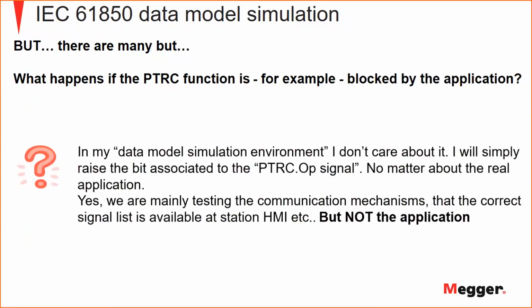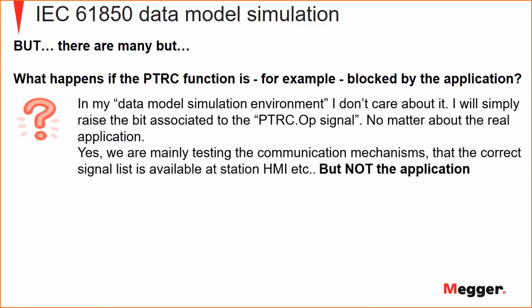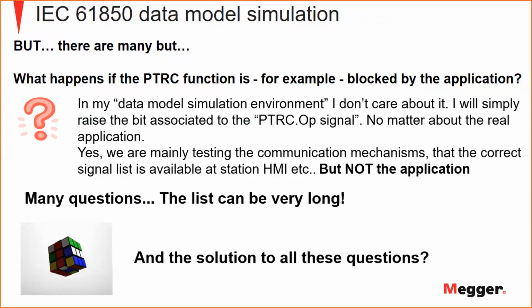And what happens if the protection function is blocked? I go in the data model and I raise a trip signal and I send a GOOSE message on the trip signal. Perfect. Unfortunately, the trip function was blocked. The data model doesn't care. So I hope I'll give you some examples, for more expert and less expert, to understand that the data model is important for many things, but it's not the solution. It does not allow me to test the application in a simulated environment. And the list can be very, very long.